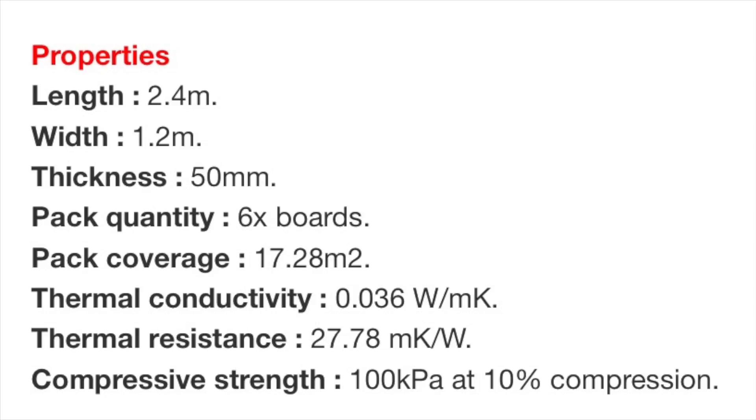And we know that the board's 50 millimeters. And I know that I've got four times that insulation. The problem here is that that's wrong. The 0.036 is the standard measurement for polystyrene, which is a meter thick. If we go back to the engineering toolbox, you'll see that the thermal conductivity for polystyrene is 0.03. Now, it doesn't say anywhere on the site, but that's actually for a one meter thick slab. So it's one meter by one meter by one meter and the thermal energy through that. Nobody tells you that.